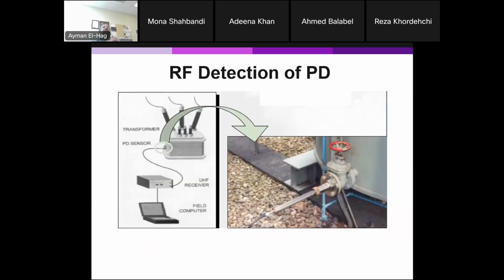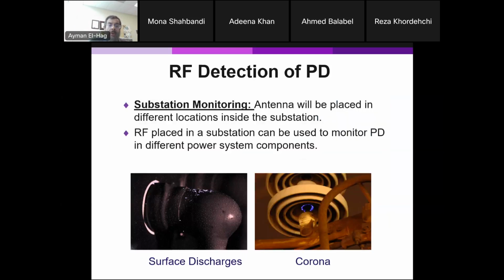Now, if you don't have access, there is still an access point, which is the drain valve. So you can insert the antenna, and you have to modify the drain valve, remove it, and this is the antenna installed inside. Now, that is good. You have an antenna inside. However, you don't have multiple antennas, so you will not be able to localize the partial discharge. You can tell if there is partial discharge or if there is no partial discharge, but you cannot localize it.